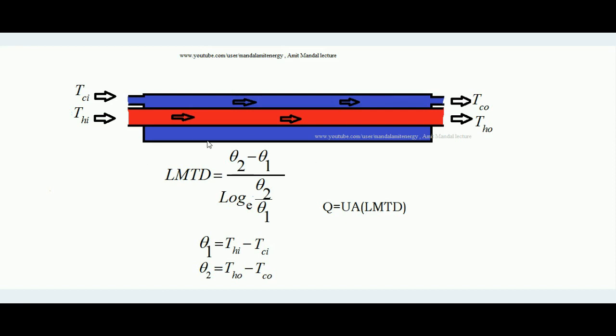Suppose this is a parallel flow heat exchanger — it is a double pipe heat exchanger. Hot fluid enters through the central pipe and cold fluid enters and flows through the outer peripheral pipe. Hot fluid enters with temperature T_HI and exits with T_HO; cold fluid enters with T_CI and exits with T_CO. LMTD equals theta-2 minus theta-1 divided by ln(theta-2 / theta-1).